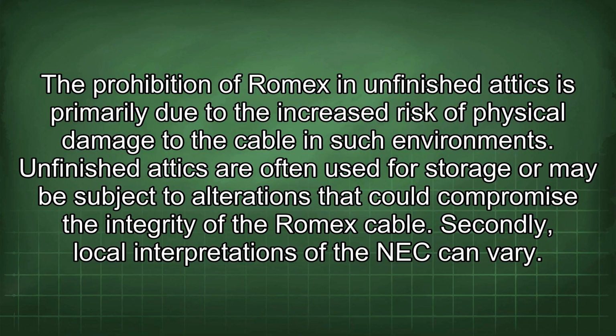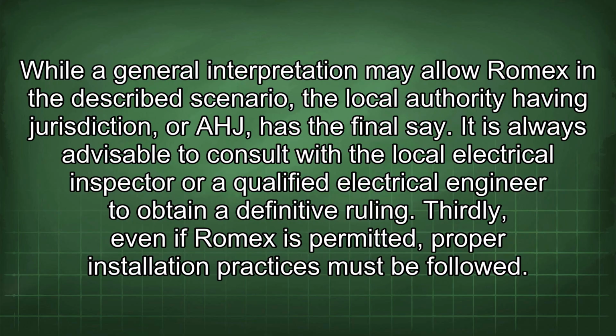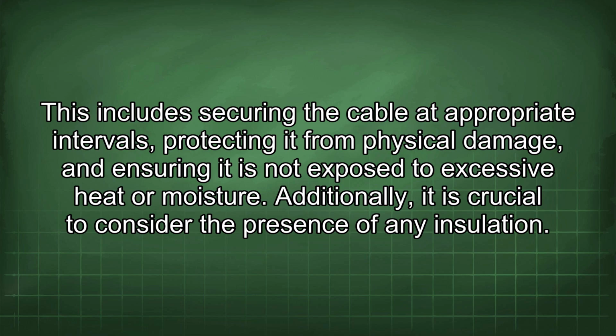Secondly, local interpretations of the NEC can vary. While a general interpretation may allow Romex in the described scenario, the local authority having jurisdiction, or AHJ, has the final say. It is always advisable to consult with the local electrical inspector or a qualified electrical engineer to obtain a definitive ruling. Thirdly, even if Romex is permitted, proper installation practices must be followed. This includes securing the cable at appropriate intervals, protecting it from physical damage, and ensuring it is not exposed to excessive heat or moisture.